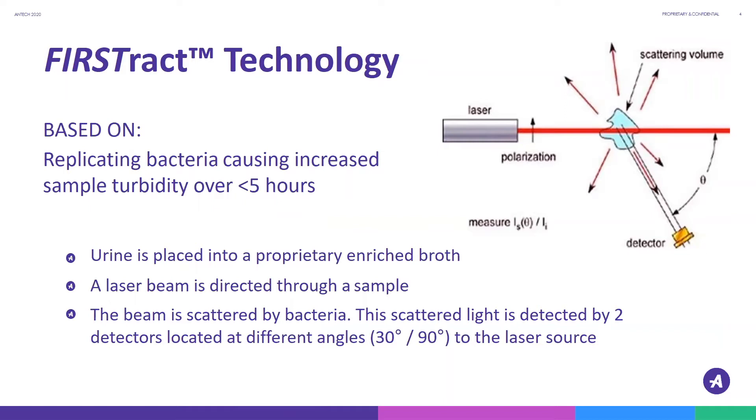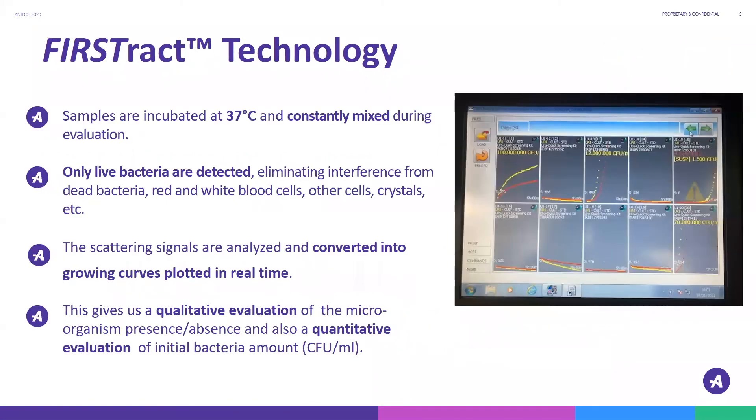As the bacteria replicate, the amount of scattered light increases, indicating the presence of live bacteria. All FIRSTract samples are incubated at exactly 37 degrees Celsius and are constantly mixed during an evaluation. This helps avoid sedimentation or flotation of other cells or organisms during analysis.